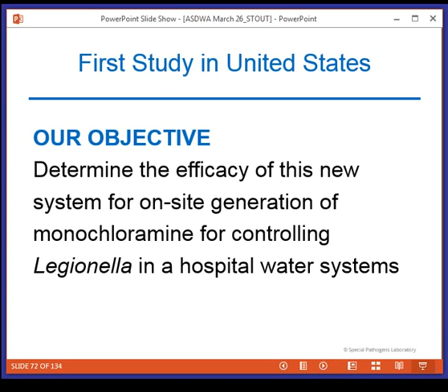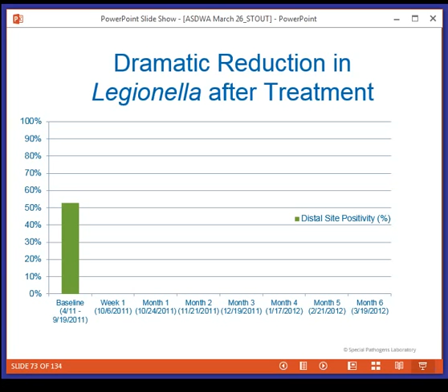So this is what I want to show you: percent positivity of distal outlets over time. We start out with over 50% of the outlets positive for Legionella pneumophila serogroup 1. At one week, what's happening now? About 30 distal sites are tested. At one week, it dropped from over 50%, actually higher than that to start, down to 10%. Then we tracked it at 1, 2, 3, 4, 5, and 6 months.